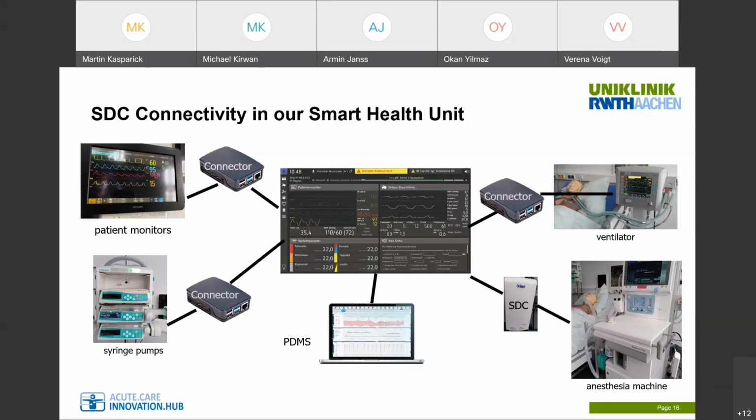If there are some patient data or vital parameters, you could use them or visualize them on the surgical side, and even on the anesthesia side, you would be able to put in the panel of the OR table, because we know that in the OR, the OR table is a lot of times controlled by the anesthesia staff. So these are some use cases we already implemented. And I don't know if your question was also regarding the use cases or regarding how we technically made it possible.